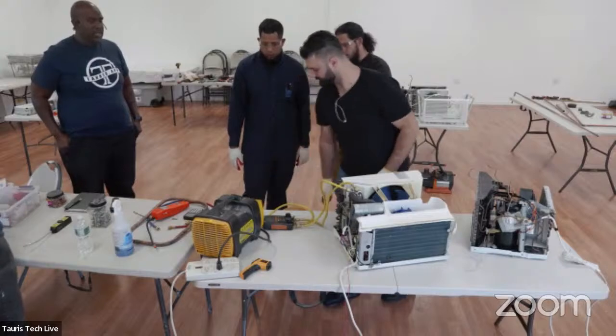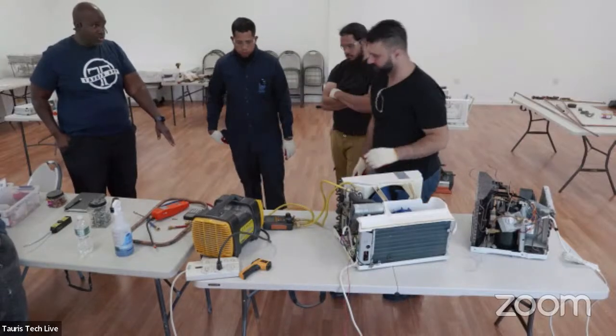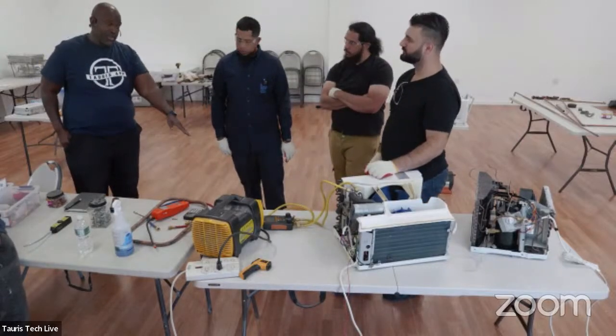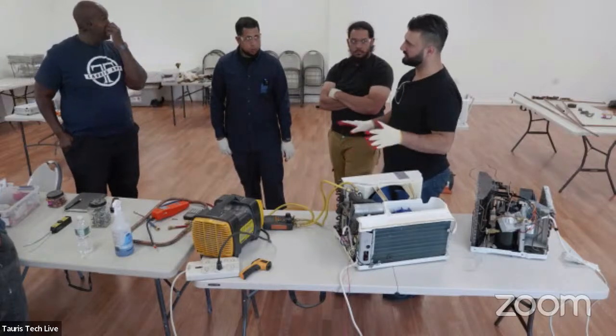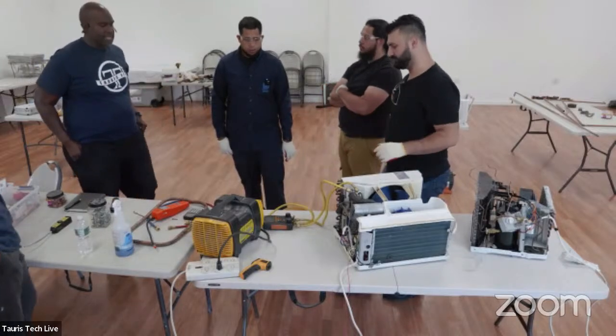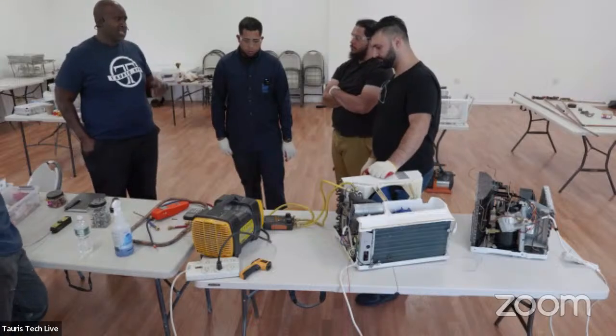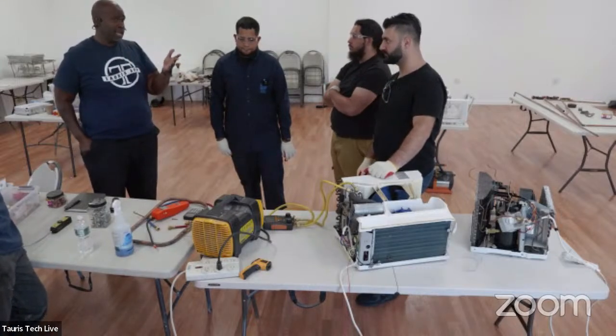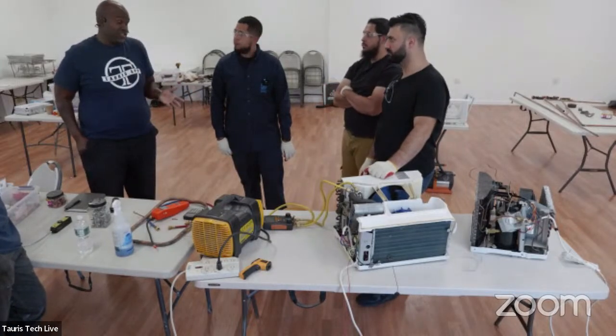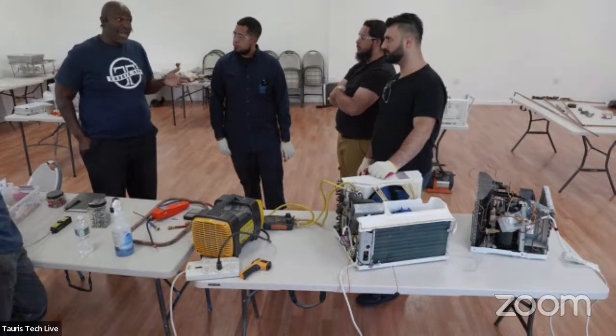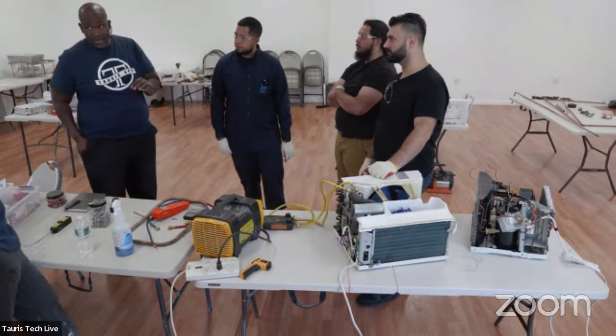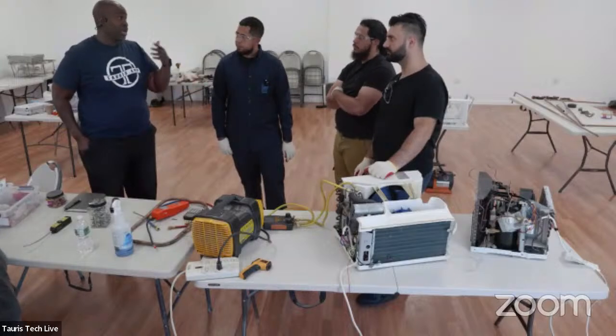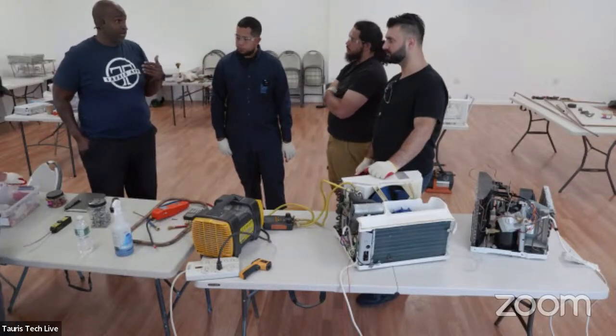Okay, now there's still refrigerant in that hose, but it's not as much as it would be. So now we minimize it - this is the minimum that we can do, that's it. I'm trying to minimize it, because sometimes if I'm working on a machine that has 100 pounds of refrigerant, I can put that refrigerant back. So I'm trying to minimize the loss of refrigerant so I can put most of it back. Okay, so then we're going to disconnect.